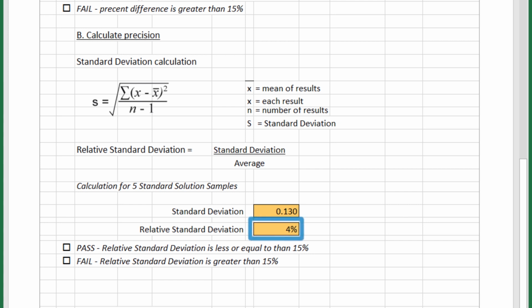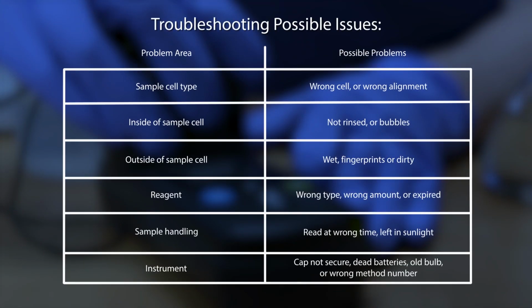If the result of the relative standard deviation is less than or equal to 15%, then the precision of the 5 replicate standards passes the IDC. If either the accuracy or precision value is greater than 15%, please try again. Here are some possible reasons that may cause the results to be outside the acceptable range. If, after multiple attempts, the issue is not found, it may be necessary to have the instrument checked or recalibrated by the manufacturer.